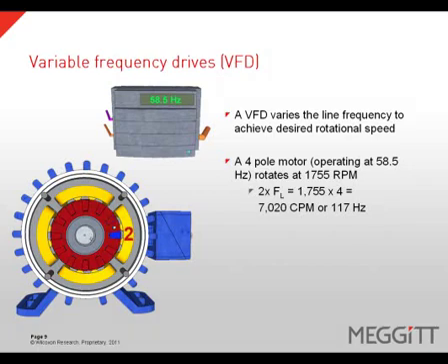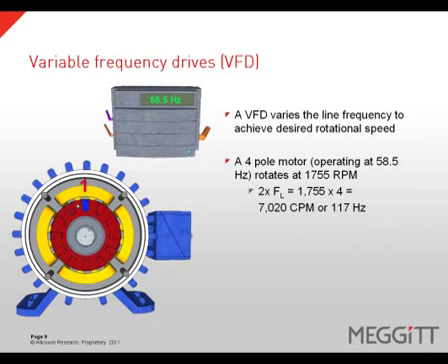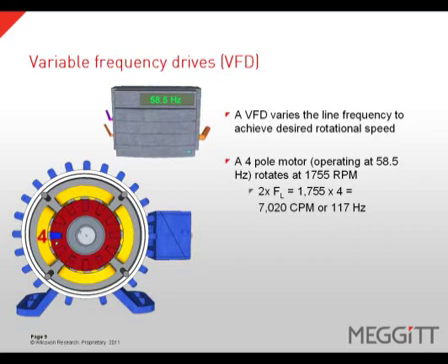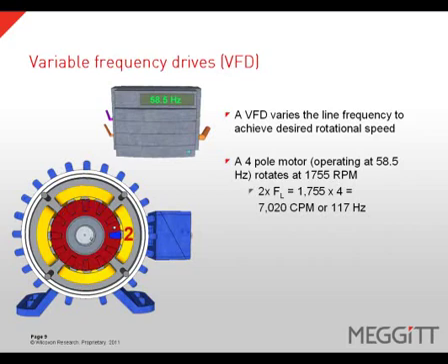With variable frequency drives, the motor speed is controlled by varying the frequency of the applied voltage. The same principle applies in that two-times line frequency vibration is created by the number of poles pulling on a rotor at a given location during a full revolution. A four-pole motor operating at 58.5 hertz rotates at 1,755 RPM. To calculate two-times line frequency, we multiply 1,755 times four poles to get 7,020 CPM or 117 hertz.